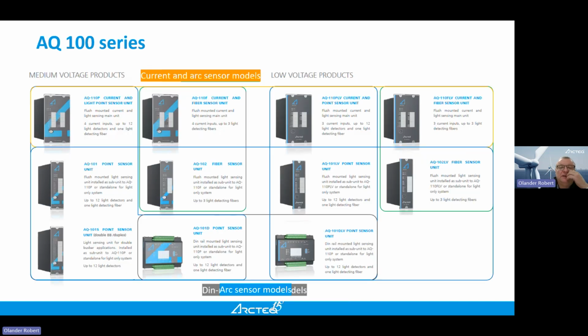Okay, I will not go into details about the products. Once again, if you need more information, we can go into details, but there are different ways of realizing an arc protection system. You can do it with point sensor models. You can do it with fiber sensor models. It means that either you put a mechanical sensor detecting the light as a point sensor, or you install a fiber in the whole switchgear and detect it everywhere. It depends a little bit. I would say that loop sensor is used very often in low voltage switchgear where you have more details, and in medium voltage switchgear very often point sensor models. But it's not so simple. There are many different ways to realize it. You can also make a mixture of loop sensor and point sensor if that is needed.